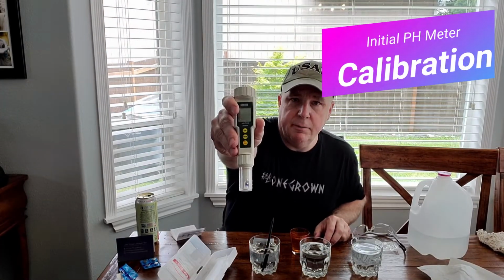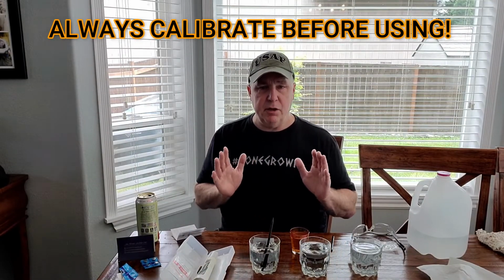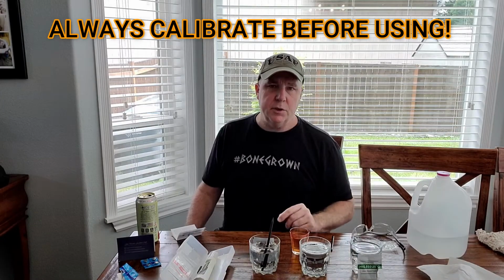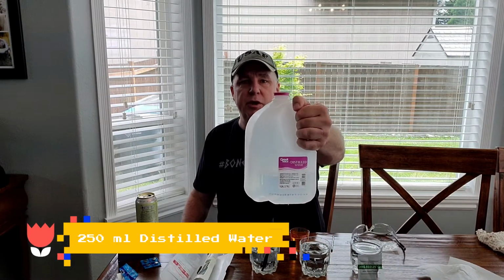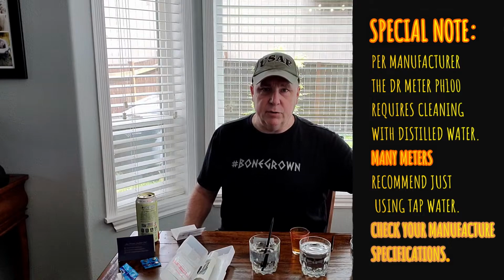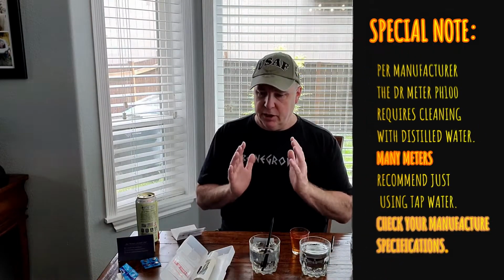I got a new pH meter by Dr. Meter right here, and I'm getting ready to calibrate it. When you first get a pH meter, the first thing you should do is go through calibration. So the things you're going to need: 3 cups that will hold 250 milliliters of distilled water. Folks, you can't use tap water on this because you need something that's basically a very neutral and clean water source. So you're doing this to calibrate your meter. So I have 3 clean cups. Each one has 250 milliliters of distilled water in it.